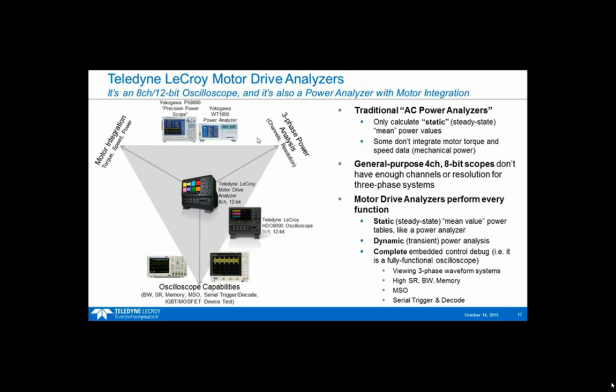These devices are typically used for static analysis—they give you numbers. The motor drive analyzer is great for static analysis; it can give you a mean value over a short or long period of time. It can also do dynamic or transient power analysis, letting you see waveforms and trends, and it can help you debug things oscilloscopes usually handle, meaning the embedded control system.